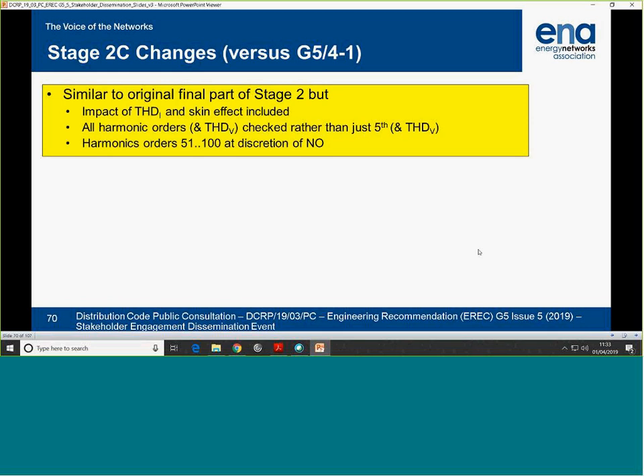It allows for skin effect, which is useful, and the assessment is not just the fifth harmonic and THDV. It is all harmonic orders because they have planning levels for every one of them. So that makes sense, especially since you're already using a spreadsheet to assess PhD to derive values, so therefore it's easy to do. The assessment goes up to the 100th harmonic, and it's at the discretion of the network operator. The reason that is in there is because with some voltage transformers at 11 kV or slightly above, you can't rely on the output of them to be accurate in the high order harmonics. So there's a discretionary aspect there. And VTs are not that good.